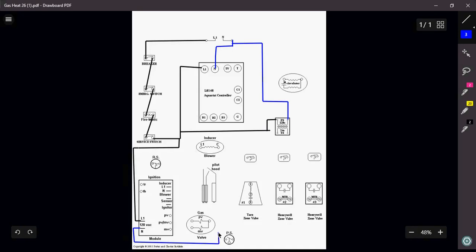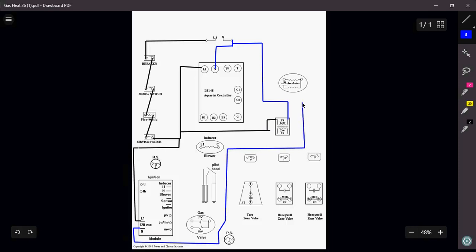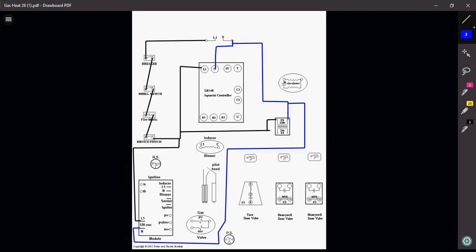Let me bring back my neutral down here. As you can tell, this diagram may start getting a little bit complicated, especially with all the wires going all over the place, but we'll try to explain it as best as we possibly can. So there is my 120-volt circuitry so far. I'm powering up my Aquastat, my transformer primary, and I'm also bringing my 120 volts down to my ignition module.